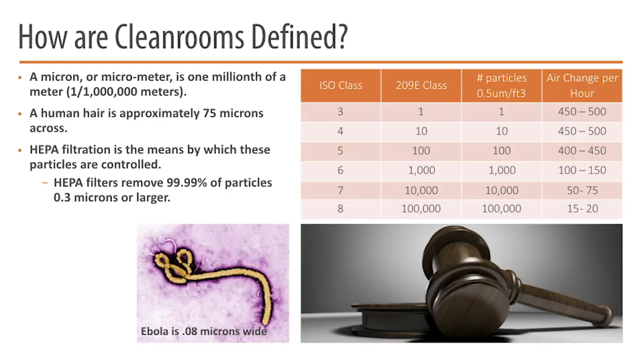So again, the ISO class, 209E class, what does this all mean? If we take a Class 100 clean room, or ISO 5, another name, what it means is you're going to have no more than 100 particles that are 0.5 micron in size and larger in a cubic foot of air. So in any cubic foot of air, you're not going to have any more than 100 particles of that size. The air changes per hour, we'll pivot back to that later. This is kind of the older way that we're getting away from, a prescriptive approach, saying that if we run the air through these HEPA filters 400 times an hour, that's going to ensure that we're at a level of Class 100, ISO 5.